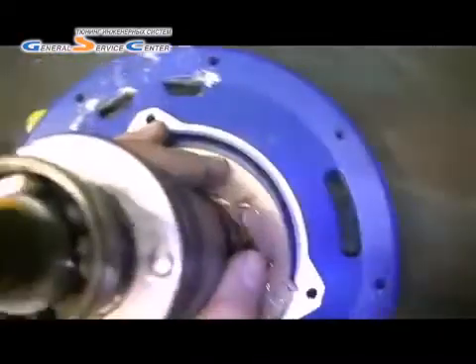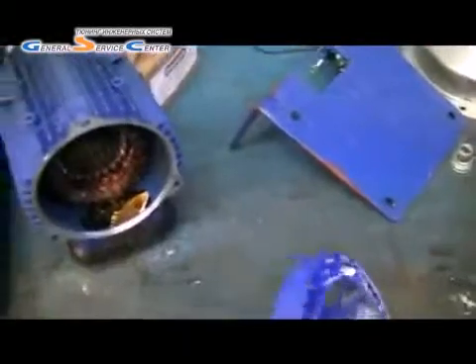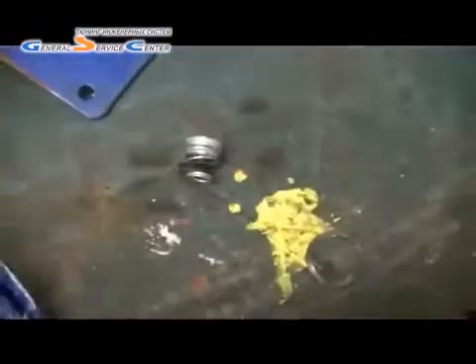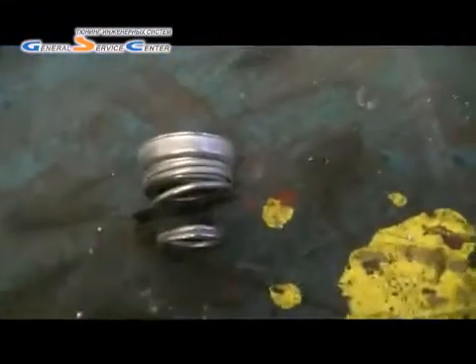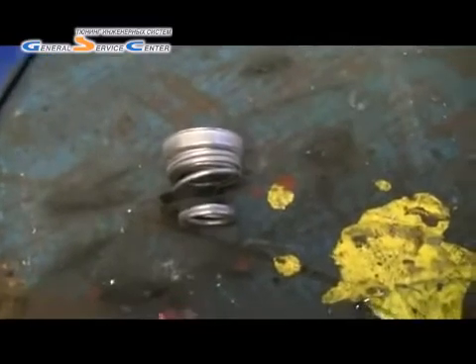So I'm quite happy and satisfied to say the bearings on this have failed, causing the motor to burn out. So that's going for scrap — the rest of it's scrap. The only good thing is the shaft seal. If you look at that, not a mark on it — it's perfect, nothing wrong with that shaft seal. So I'll keep hold of that, bag it up, mark which motor it's for, because at 2 o'clock in the morning that just might get somebody up and running.